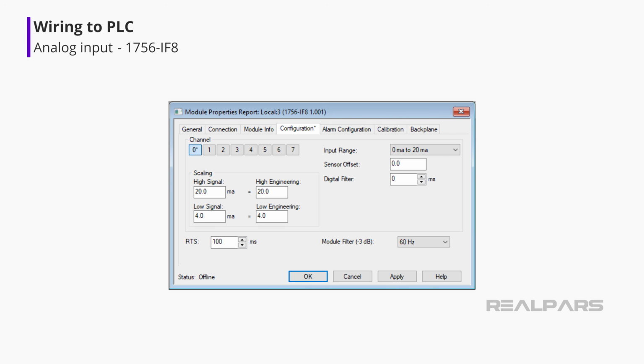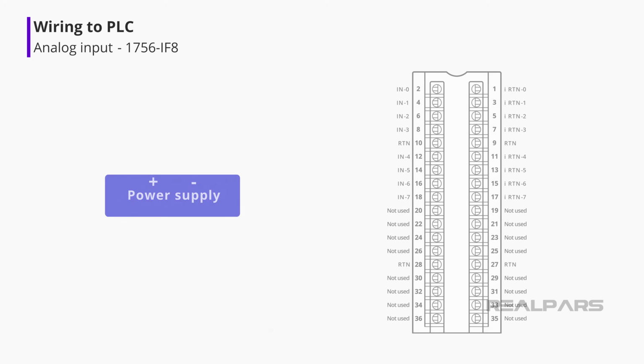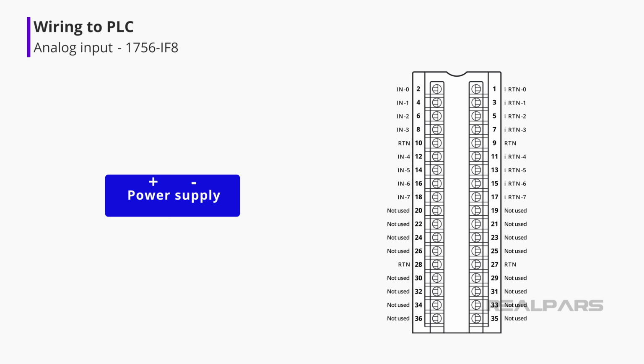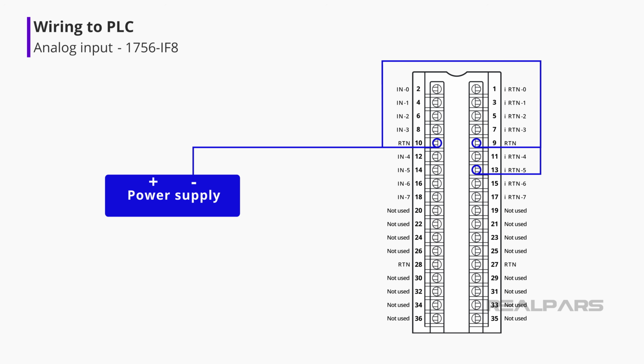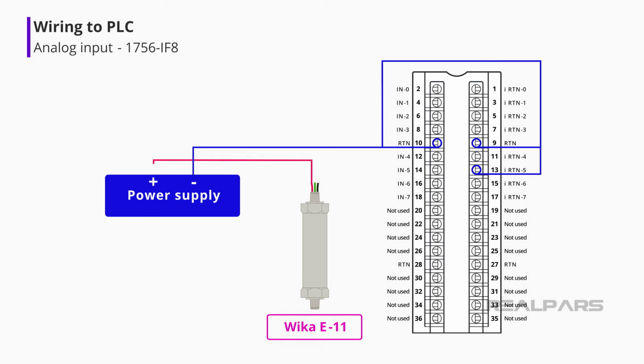The 1756-IF8 module is configured for current input during programming in the I/O configuration. We will connect the Wika E-11 two-wire transmitter to channel 5 of the analog module. Terminals 9, 10, and 13 of the analog module are connected and then wired to the negative DC terminal of the 24-volt DC power supply. The red lead of the Wika E-11 pressure transmitter is wired to the positive DC terminal of the power supply. The black lead of the transmitter is wired to terminal 14 on the analog module.